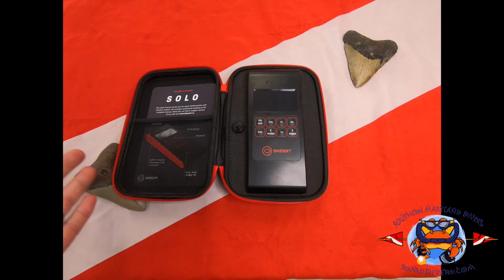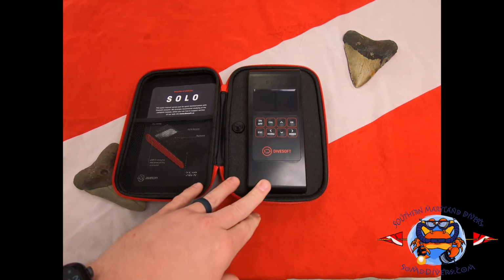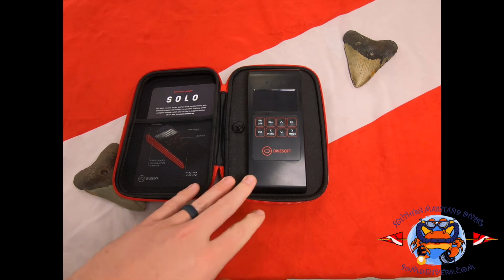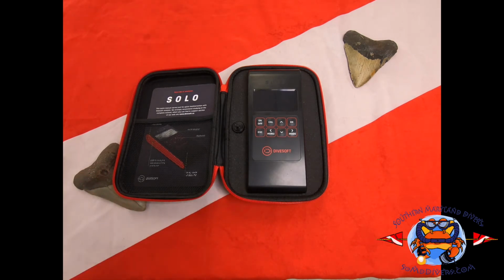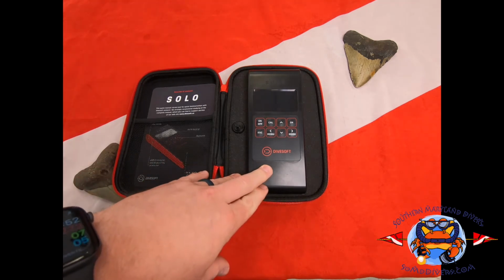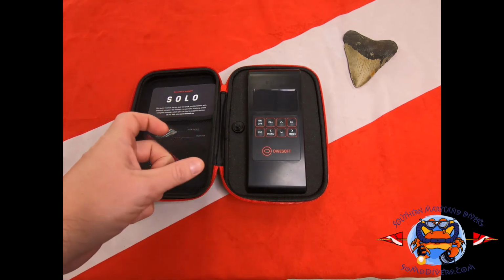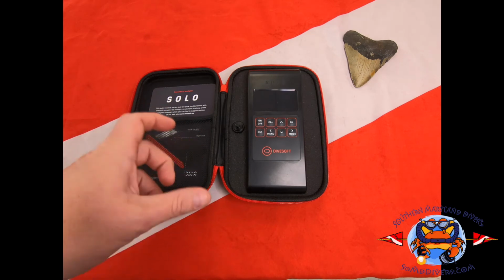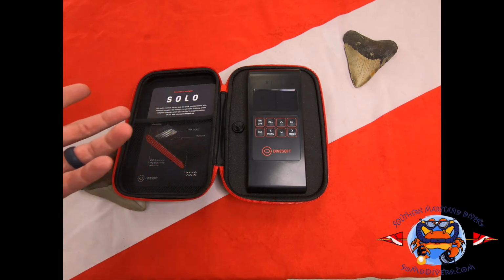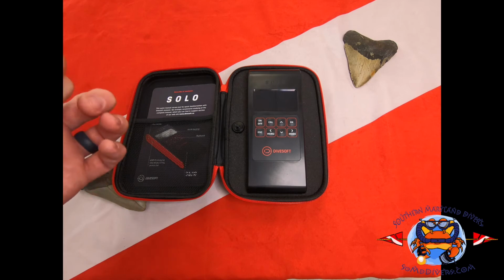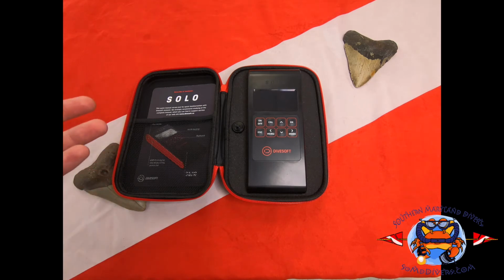Okay, so what I mentioned about the technology: up until Divesoft came out with their stuff, analyzers all used electrochemical sensors, which this one does as well. So the oxygen sensor that analyzes the oxygen content of the mix is actually an electrochemical sensor, and it gets replaced every 2-3 years. Whenever you start having problems with it, it'll get replaced.